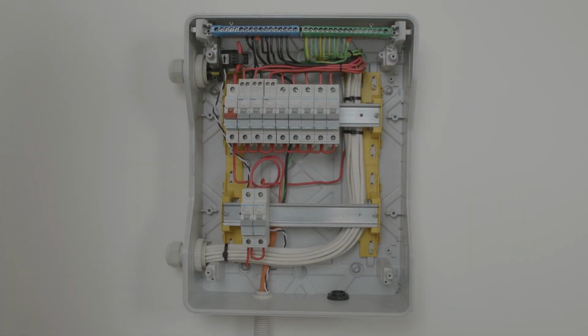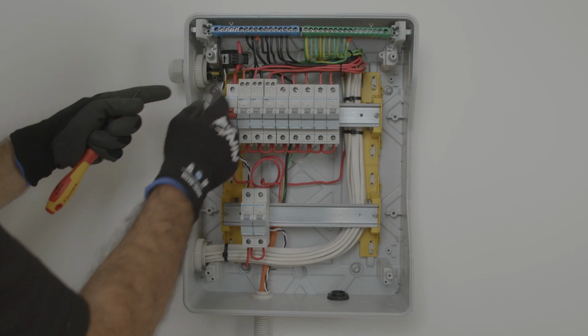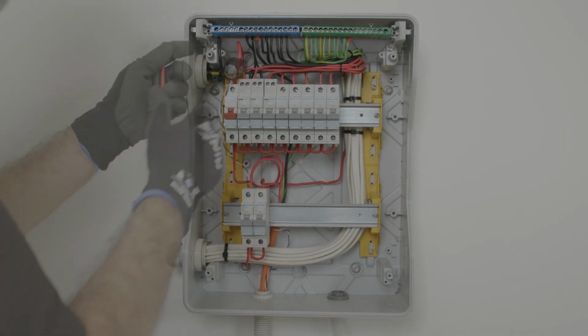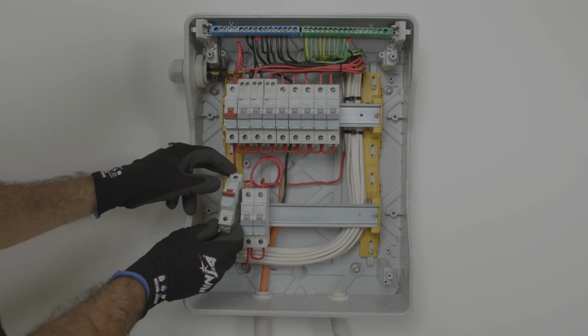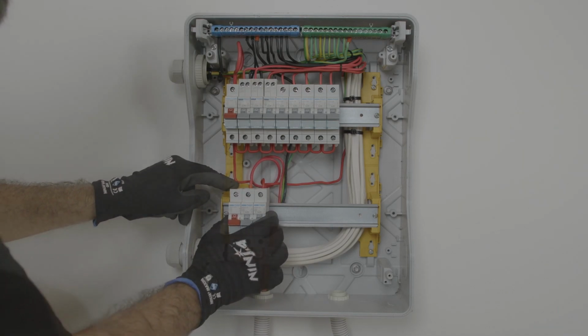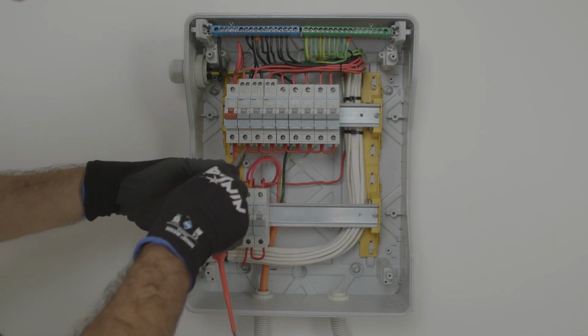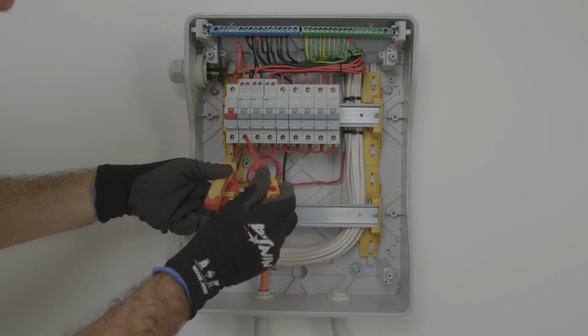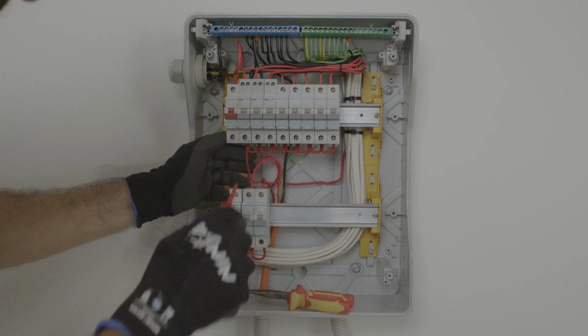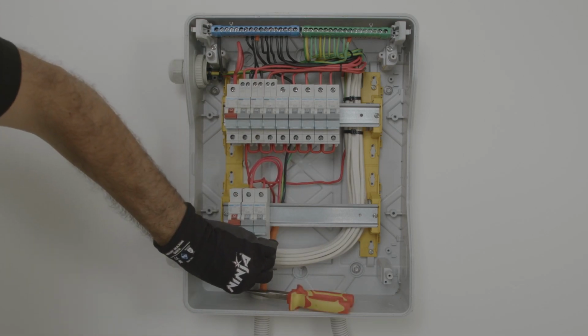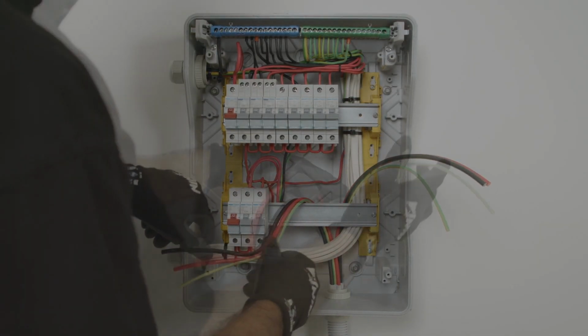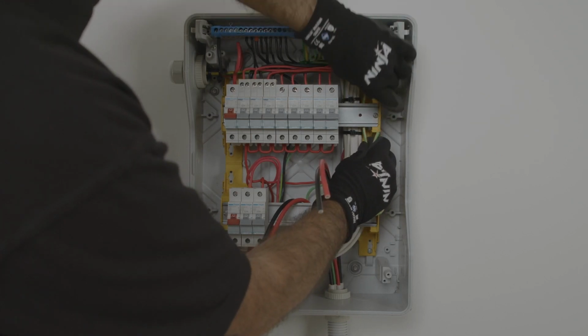So the backup interface, if wired for whole home backup, as we are showing here, is wired between the grid supply and all of the loads. So what we're doing here is we're taking the incoming supply from the grid, then from that, we're taking it to an MCB, to the backup interface, from the backup interface, back to this board to its own dedicated MCB, which then supplies all of the home load circuits.